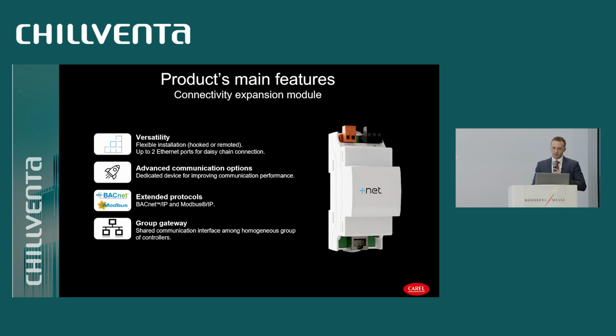If we move our attention to the +net, we can say that this device is responsible for enhancing the communication performance with the possibility to open advanced communication options like BACnet over IP or even Modbus over IP. Up to 2 Ethernet ports. Even if it is not shown in the picture, you can come to our booth and you will see the module with a double Ethernet in order to daisy chain the local network. Another interesting point of this device is that it can act as a gateway. So it can combine up to 5 devices with a single +net in order to enable the Ethernet communication.